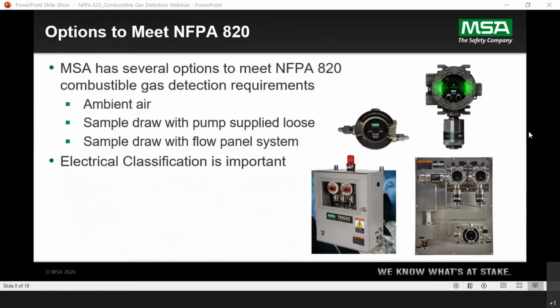MSA has several options to meet 820. I've divided what we do into 3 categories. The first one is ambient air, which is our standard diffusion type monitoring. Then sample draw is for situations where you have bad access or flooding; you could use a sample draw system. We can provide the system either supplied loose, with pumps and the detectors themselves, or integrated into an engineered flow panel. The important thing is that electrical classification needs to be understood for all this before you get started on design.